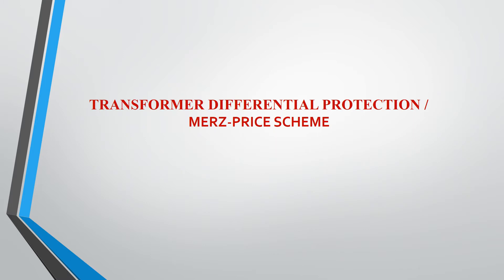Differential protection is also known as the Merz-Price scheme, or you must have heard the name biased differential protection or percentage biased differential protection in various books. We have studied this type of protection in generators and induction motors too. But in case of transformer, there are some considerations for CT which need to be taken care of before applying the differential protection, so this becomes an important topic for transformer protection.